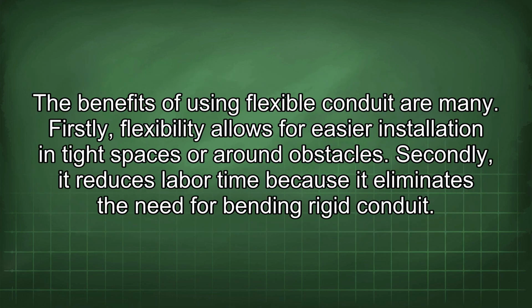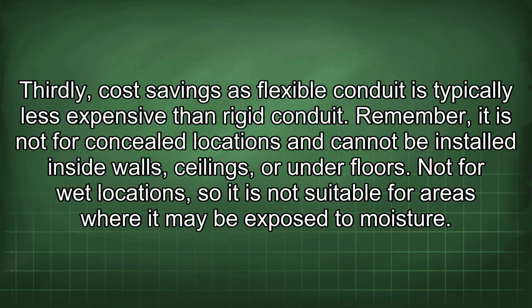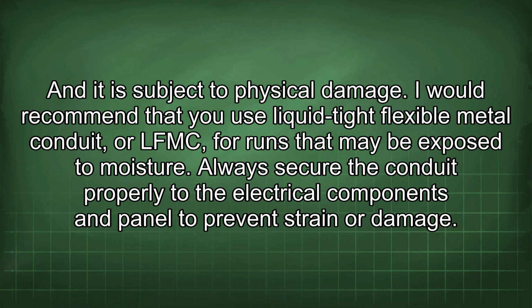The benefits of using flexible conduit are many. Firstly, flexibility allows for easier installation in tight spaces or around obstacles. Secondly, it reduces labor time because it eliminates the need for bending rigid conduit. Thirdly, cost savings, as flexible conduit is typically less expensive than rigid conduit. Remember, it is not for concealed locations and cannot be installed inside walls, ceilings, or under floors. Not for wet locations, so it is not suitable for areas where it may be exposed to moisture, and it is subject to physical damage.